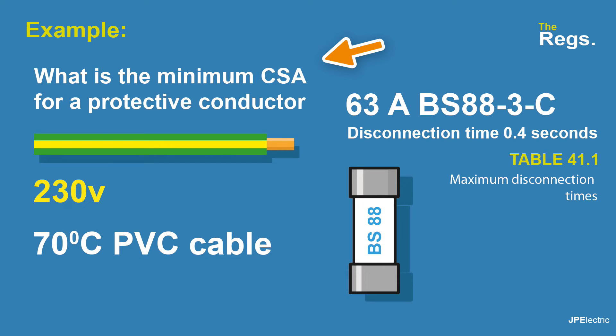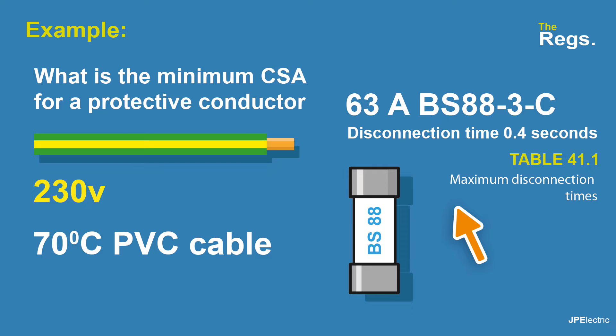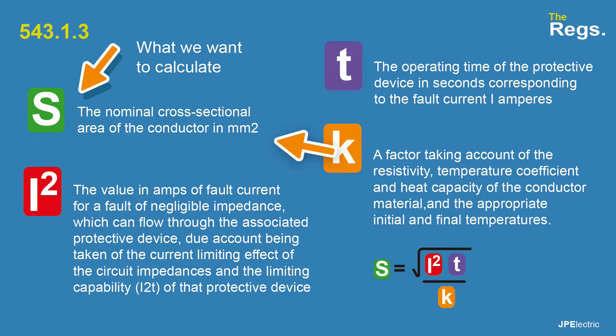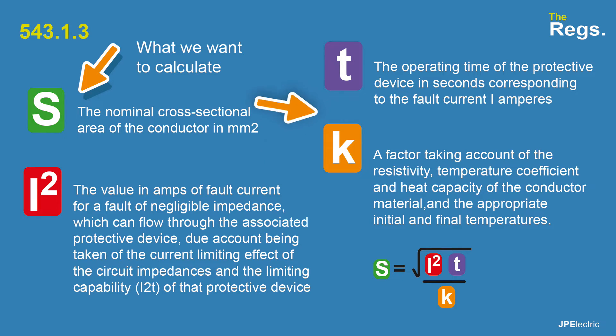Here's an example. What is the minimum cross-sectional area for a protective conductor with this set of values? It's at 230 volts, the cable is 70 degrees C PVC cable, the protective device is a 63 amp BS88-3C, and we require a disconnection time of 0.4 seconds. The adiabatic equation is: S equals the square root of I² times T, divided by K. S is the nominal cross-sectional area in millimetres squared, I² is the fault current in amps, T is the operating time of the protective device, and K is a factor found in a table in BS7671.